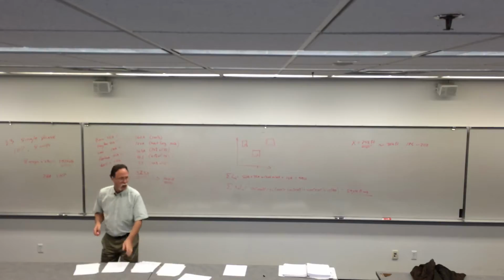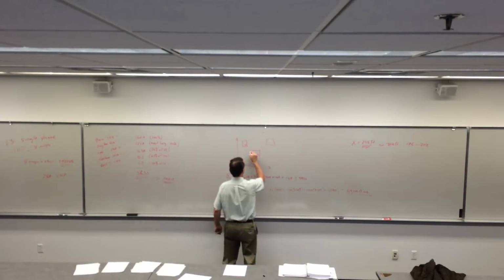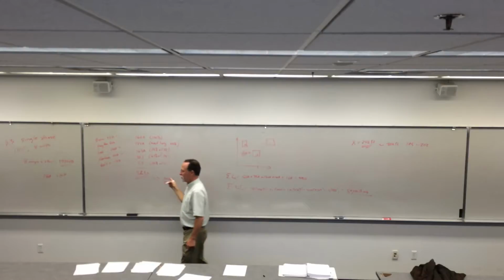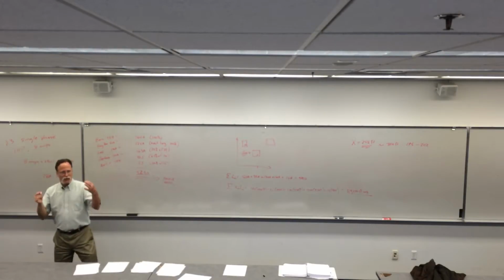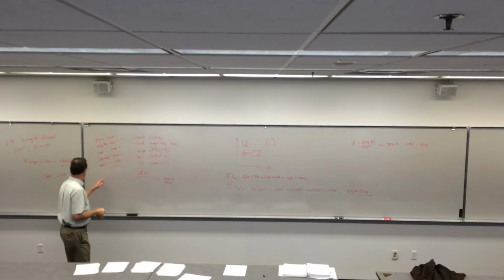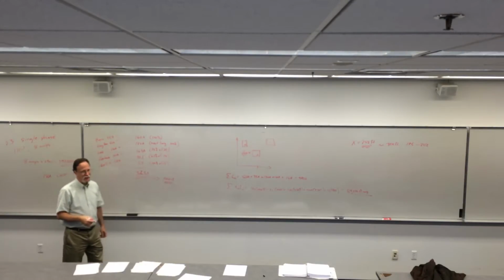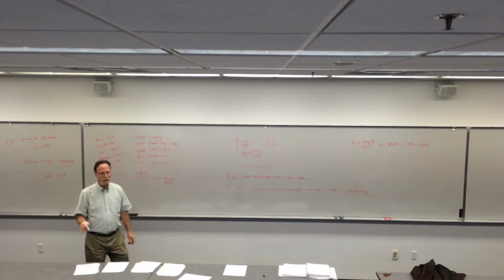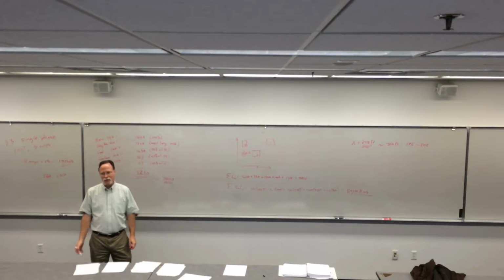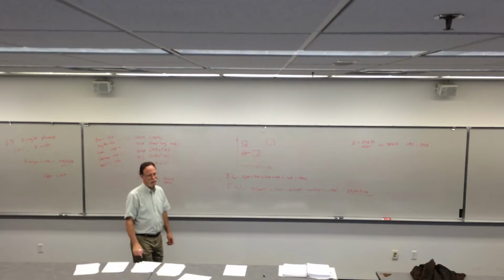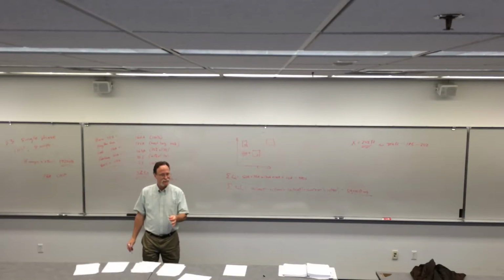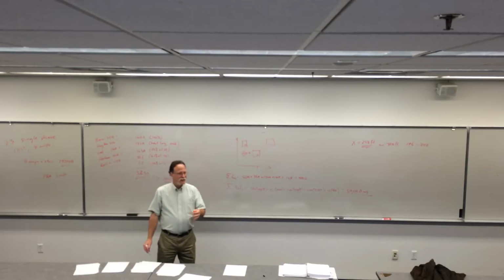So I have my main service pole somewhere in here, and then I have a well pump over here somewhere else. If I put that well pump right there out in the open, I can actually have it be 15 amps. If I put the well motor, bladder tank, everything in a little building, then I have to argue about what should be the service to that little building. 15 amps? That's the question. Why do they have to have a light in the building or something? Then you get an argument.